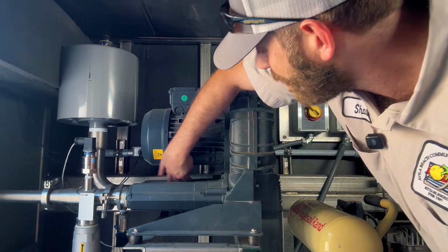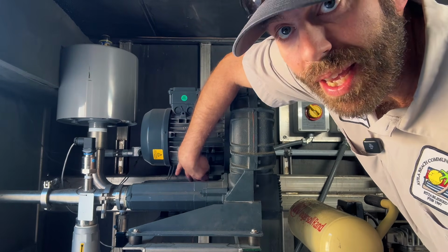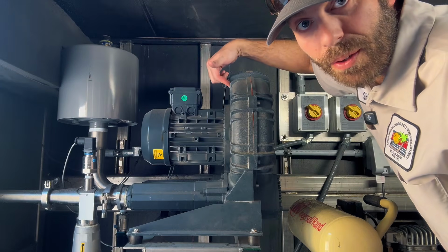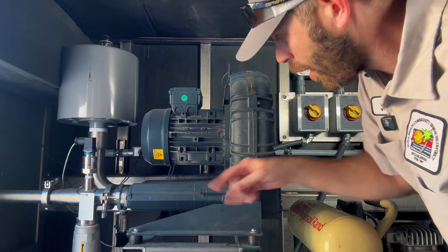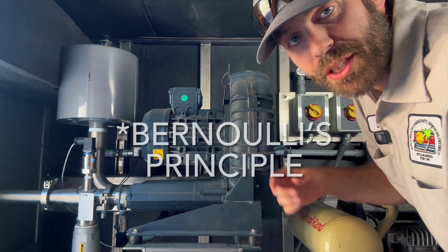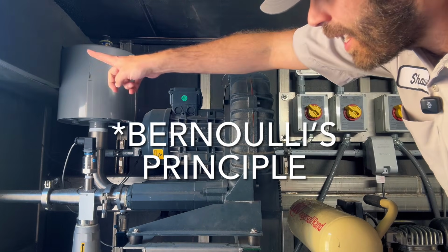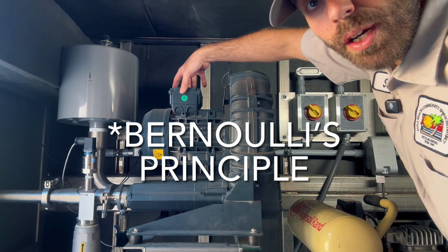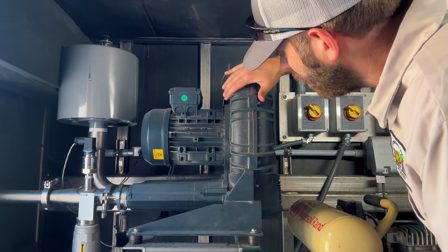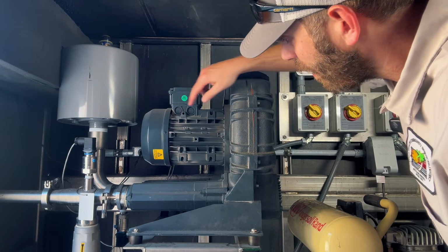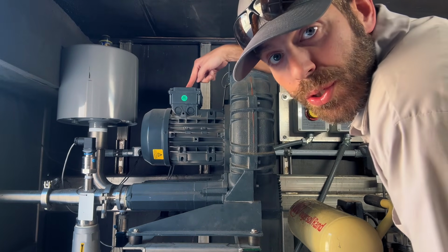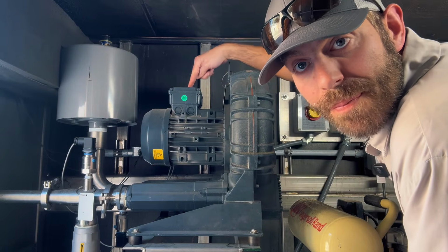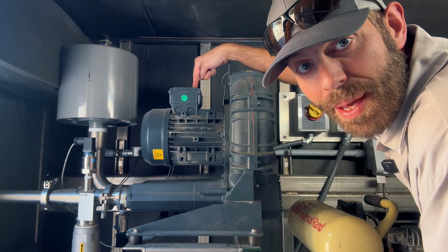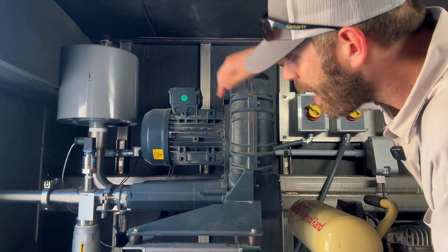The intake right here, and then this is the suction of the impeller housing, okay, the volute. And then here's your discharge. It uses the Bernoulli effect to create that suction, and it pushes it out. The motor is mounted to the casing, this volute here, and this is what's actually spinning. We can use our controls to tell the motor to slow down or speed up depending on how much air we need, okay? And then it comes out this way.